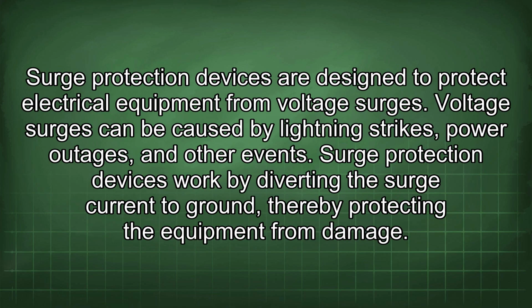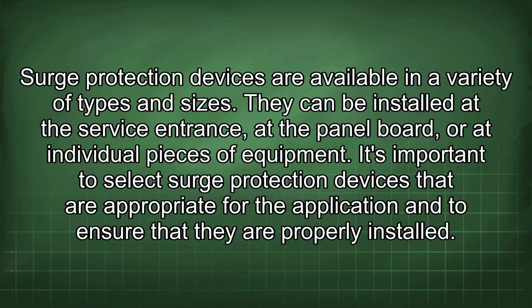Surge protection devices are designed to protect electrical equipment from voltage surges. Voltage surges can be caused by lightning strikes, power outages, and other events. Surge protection devices work by diverting the surge current to ground, thereby protecting the equipment from damage. Surge protection devices are available in a variety of types and sizes. They can be installed at the service entrance, at the panel board, or at individual pieces of equipment.